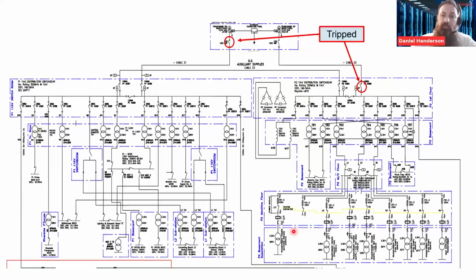I've then gone to this substation over here, which is the nearest one. So I've just gone from a logistical perspective as quick as my legs can go. In this location where I've got an 11 kV switchboard, and this circuit breaker here is tripped again on overcurrent, but there's no sign of any damage. The integrity, everything looks intact. There's no signs of overheating or burning or smells. There's no indication of anything going wrong in that area.